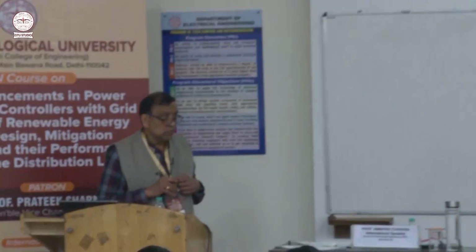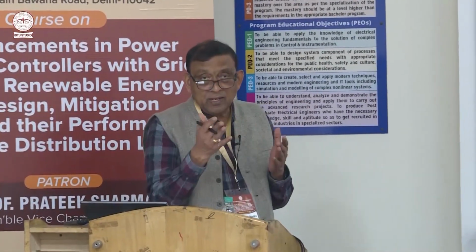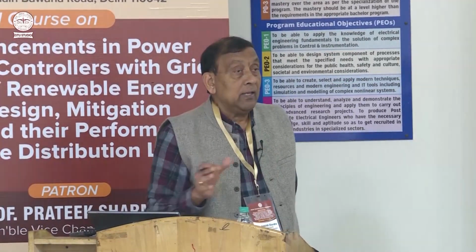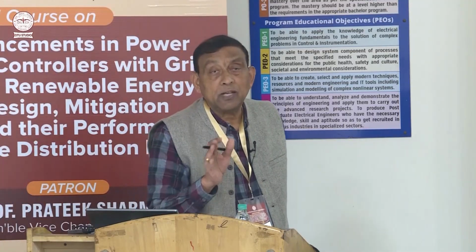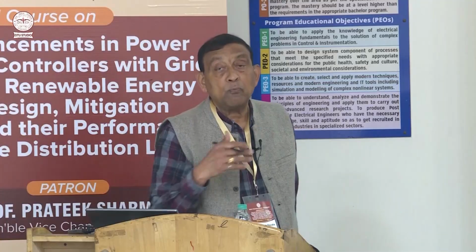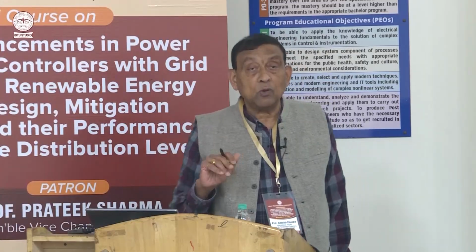Now comes a very interesting thing. Harmonic elimination. Why were we studying all this phase shift? Now is the time to apply whatever theory we have learned. So this is what I was talking about yesterday when I was giving a speech. There is a factory plant, there is one line of production, and it is generating some 5th and 7th harmonics, but they are not polluting the network much. So engineers and everybody is happy that it is not much pollution.